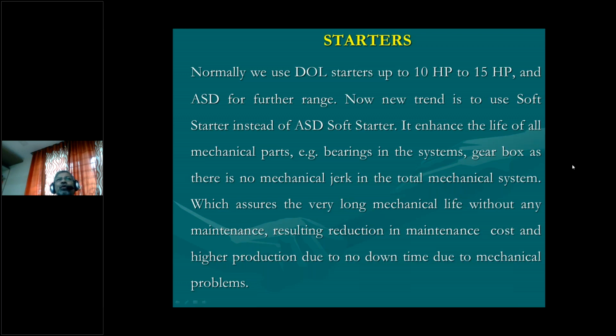Now let us move to starters. Normally we use DOL starters up to 10 HP, 15 HP and ASD for the further range. The new trend is to use a soft starter instead of ASD. Soft starters enhance the life of the mechanical parts. See, when we talk about energy, it may be anything. Suppose there is a 50 HP or 100 HP motor used as a prime mover for some equipment, like a ball mill or something like that.